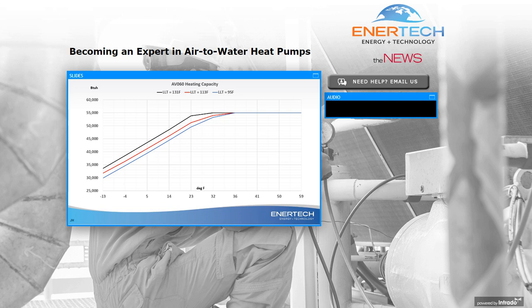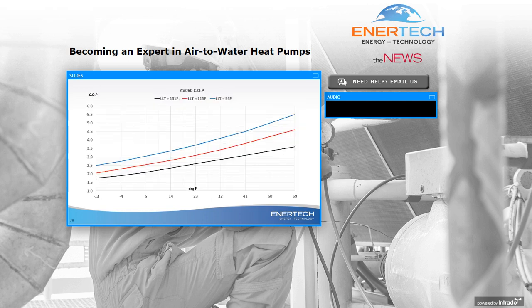We do get a little bit higher capacity with higher water temperatures. You can see here the black line is 131 degrees Fahrenheit. The blue line is 95 degrees, so that might be a radiant floor. And the red line is somewhere in the middle, which may be a forced air zone we might use a fan coil for. So our higher capacities are great for domestic hot water use. We would want higher temperatures typically with domestic hot water, but if we don't need it, we might as well take advantage of the blue line and have higher efficiencies.